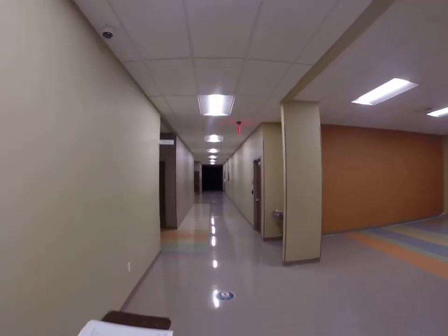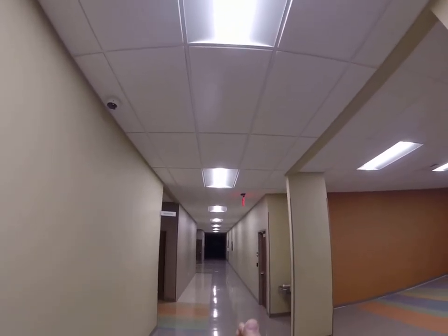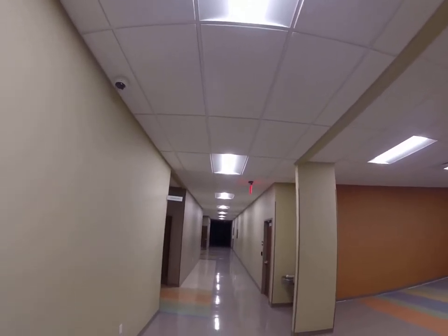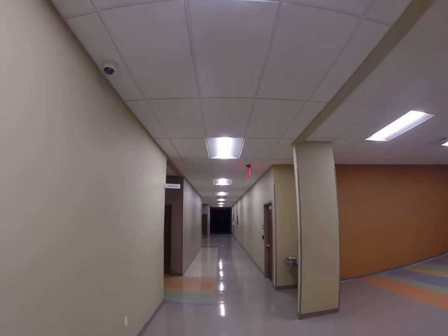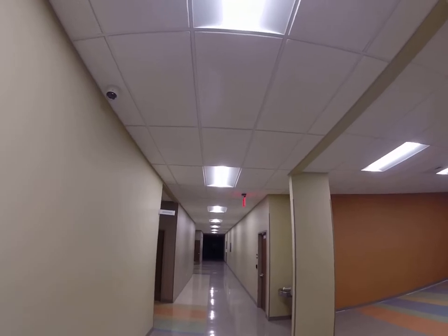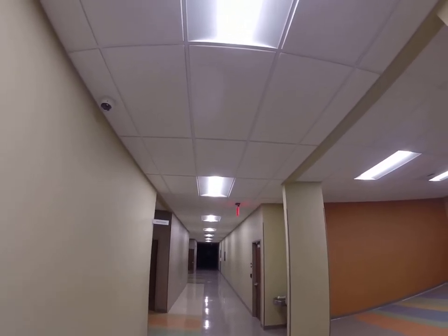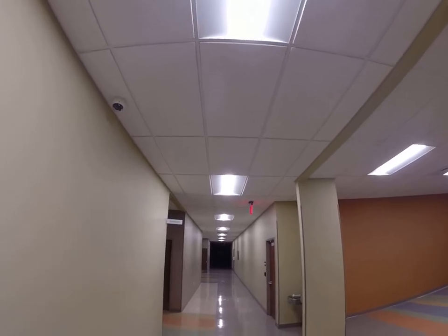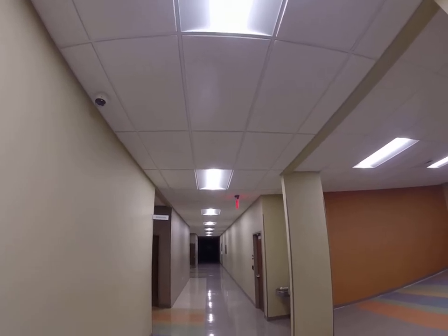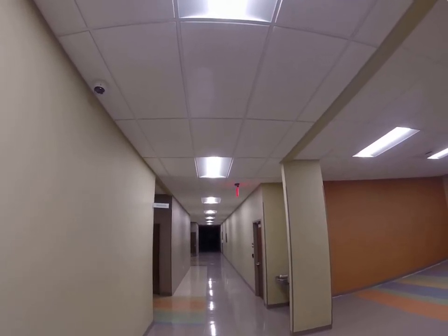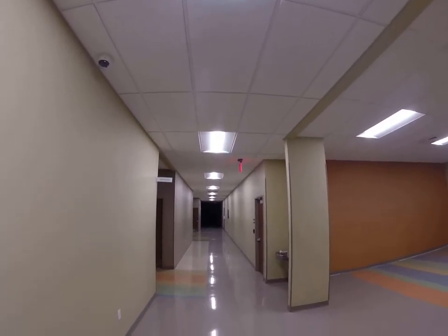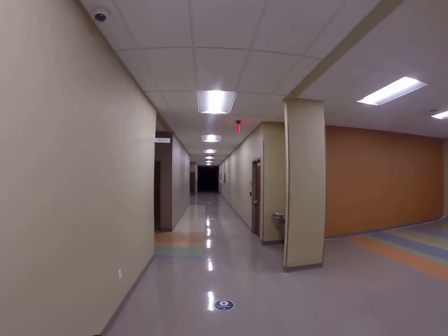Once again, I mentioned this in a previous video, the reflected ceiling plan would show exactly where these light fixtures are and how many pads are in between each light fixture. And as a general rule of thumb, it kind of helps contractors out for locating and measuring. Each fixture in the ceiling is 4 feet long, or each ceiling pad is 4 feet long by 2 feet wide. So if you were trying to measure something, you could simply count ceiling pads, multiply it times 4, or 2 if it's a 2 by 2 grid, and then you would have your measurement from one end of the hall to the other if you didn't feel like taking out your tape measure.